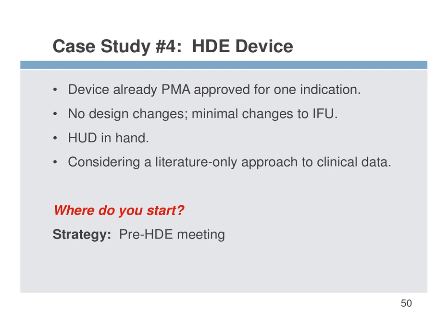So that would be the main distinction, because a pre-HDE, pre-PMA, and pre-510K can all be pre-subs. And the confusion is because the pre-subs are part of the pre-sub guidance document, but so are other meetings that aren't pre-subs, such as informational and submission issue meetings.